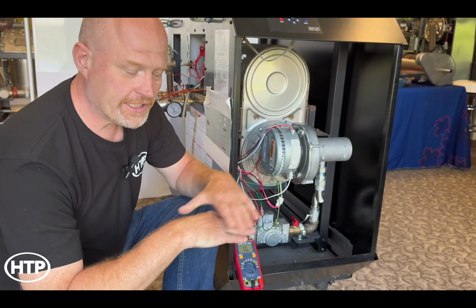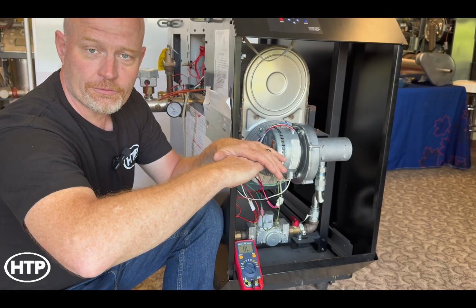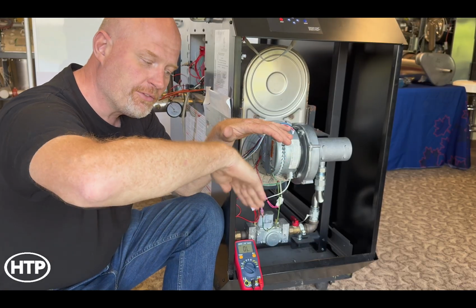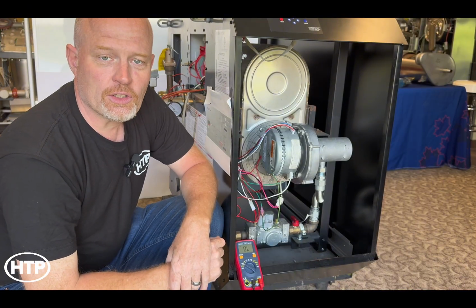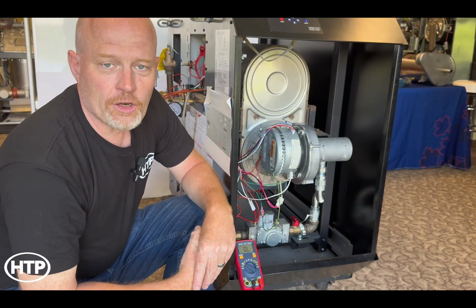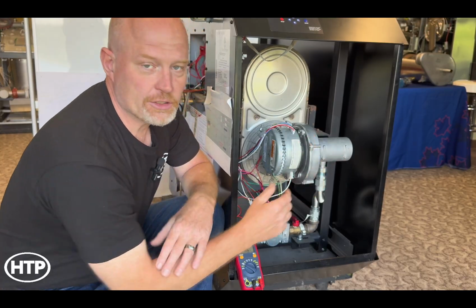So what the flapper is there to do basically is it will open up when the fan comes on, allowing airflow into the boiler, and when the boiler shuts off, it will fall down, blocking backwards airflow in case your boiler happened to be installed in a common vent system. And it also just prevents backwards migration of flue gases, which would damage your blower and venturi.